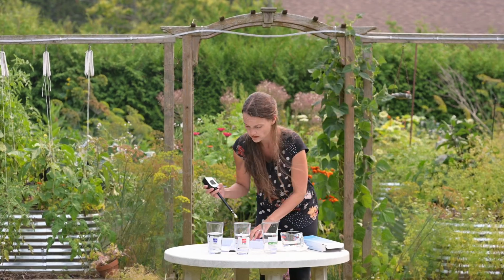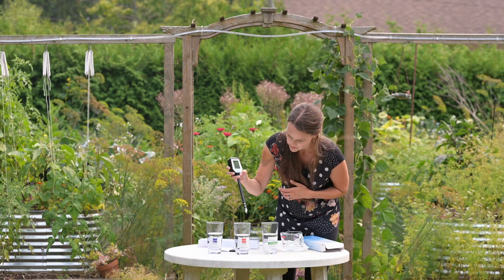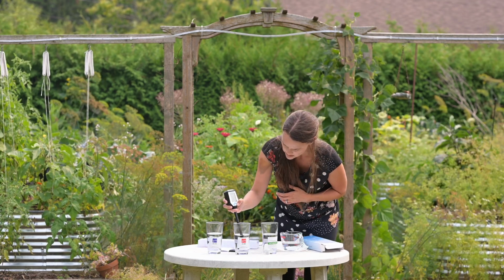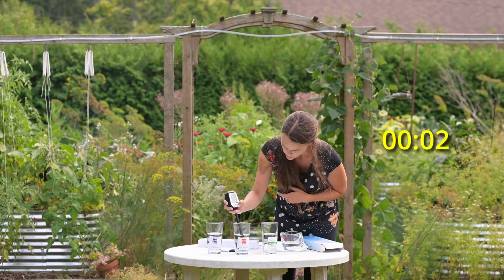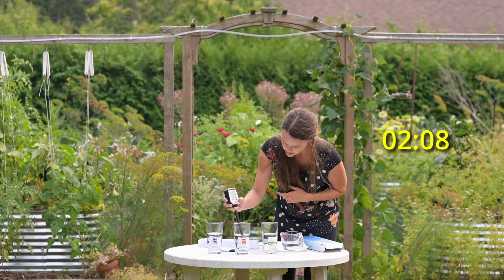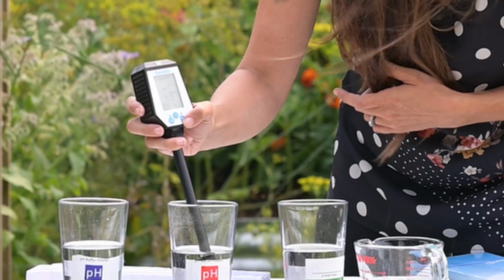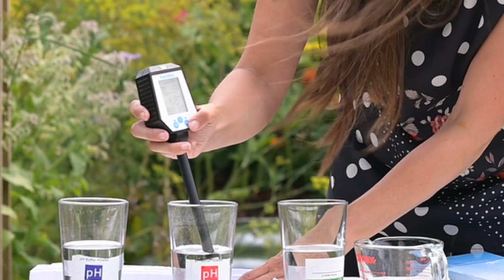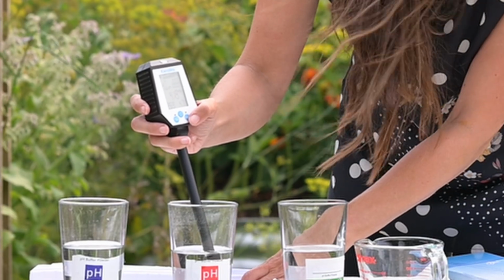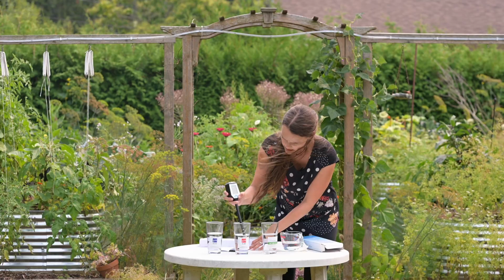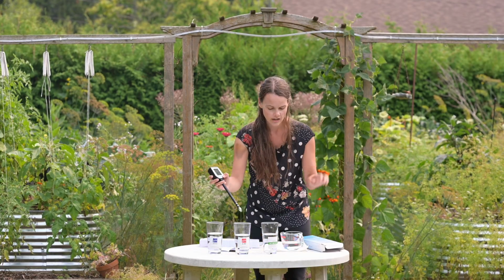I don't know what I'm doing differently. Put it in the 4 solution. Stir, press calibrate. pH is blinking. 1 1000, 2 1000, 3. Let go. 7 is blinking. Great, press calibrate. 4 blinks. 1, 2, 3. And we've pH calibrated to 4.